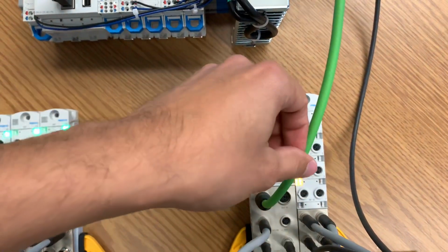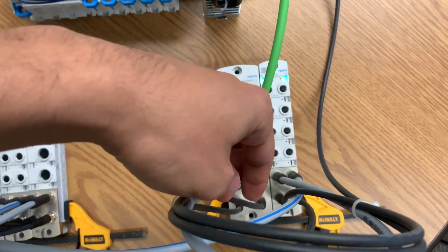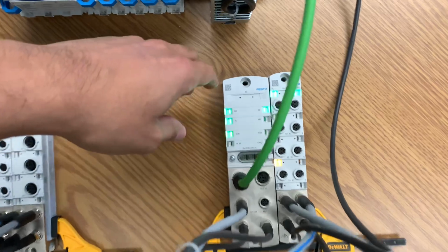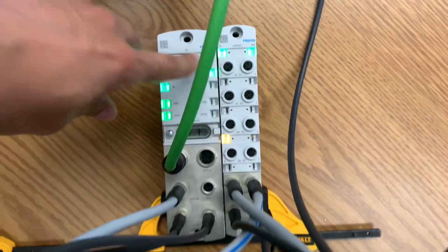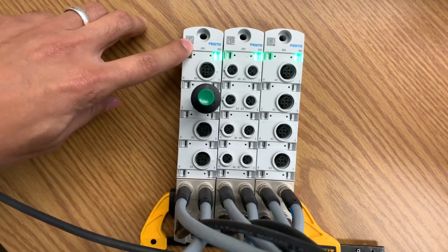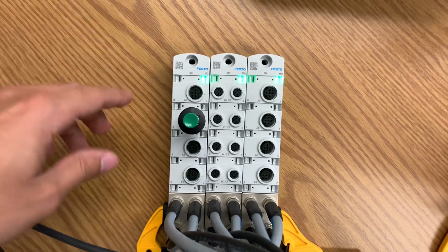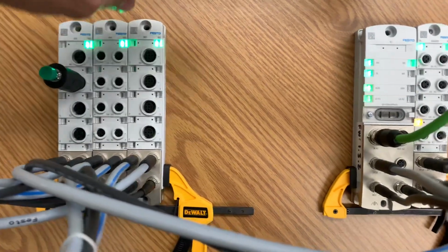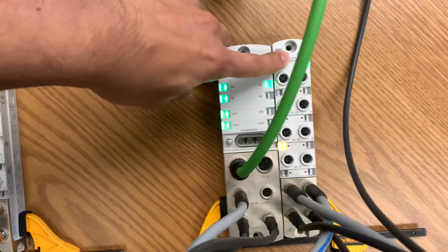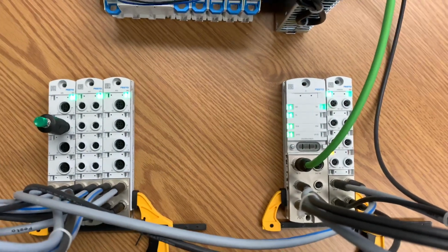Now, once I communicate over EtherCAT, I can branch out from this module to several different modules. Like in this case, this one over here is a 4 digital input, 4 digital output module. Then from here, I go to the next module by a daisy chain connection. In this case, this is an 8 digital input module, another 8 digital input, and another 8 digital input. So you can see 3 modules here, another module here. So now I have 24 plus 4. I have 28 inputs, 4 outputs right now in front of you.